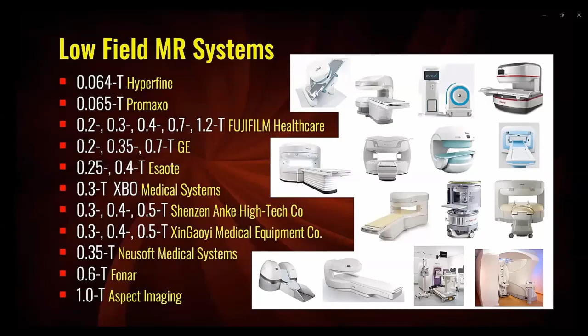Hyperfine's point-of-care portable Swoop MR imaging system operating at the very low field strength of 0.064 Tesla is a unique scanner that allows neuroimaging of patients in virtually any clinical setting, including the emergency department and the intensive care unit. This vertical field scanner has a maximum spatial gradient magnetic field of 700 Gauss per centimeter. When it is used for imaging, it never exceeds a head-specific absorption rate or SAR value of 0.009 watts per kilogram. The Swoop system has a unique feature called the Gauss Guard, which expands to demarcate the 5 Gauss line when it is stationary or moving into a patient's room to perform an MRI exam of the brain.